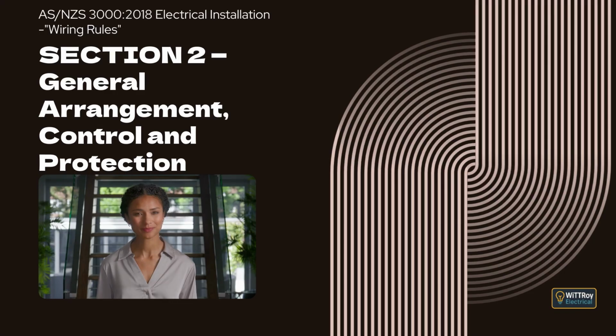The clause also reminds us that common neutrals can rise to dangerous voltage if they are disconnected while active conductors from different circuits are still connected, so the design must avoid that situation. The neutral must have enough current carrying capacity to match the associated active conductors.